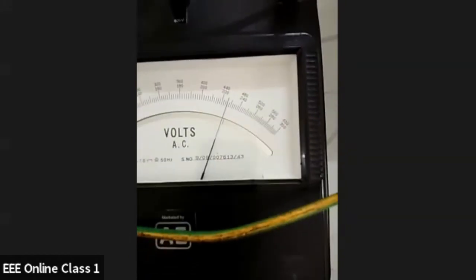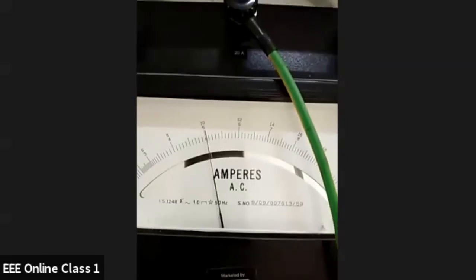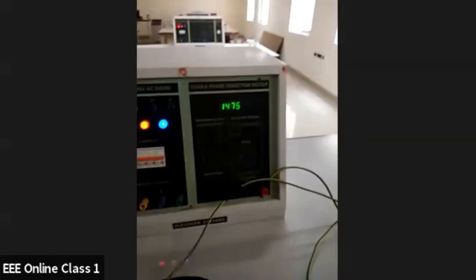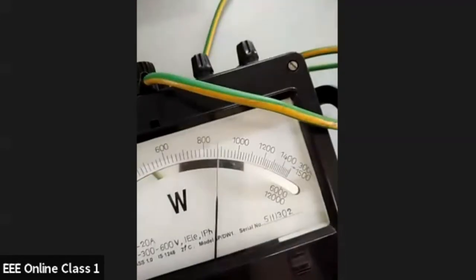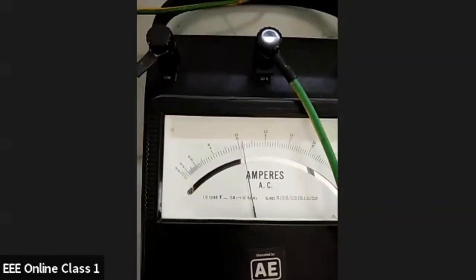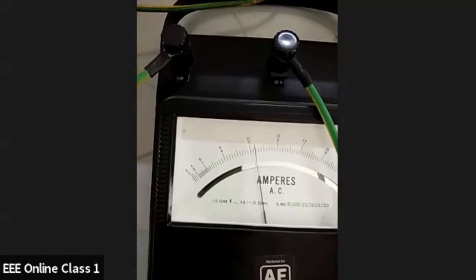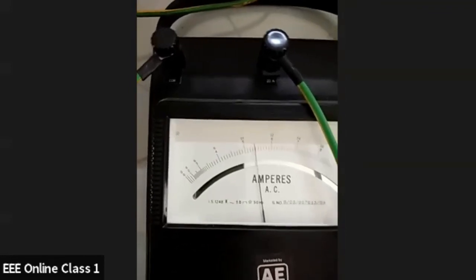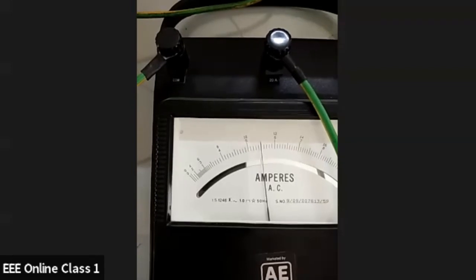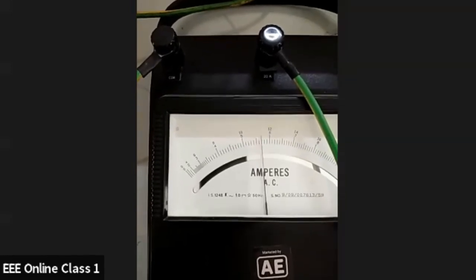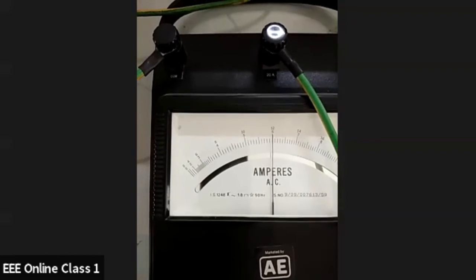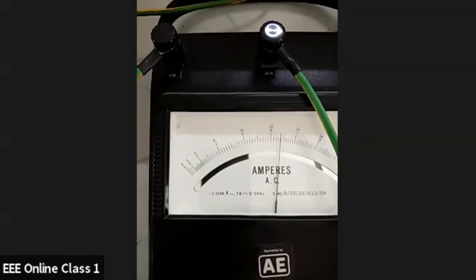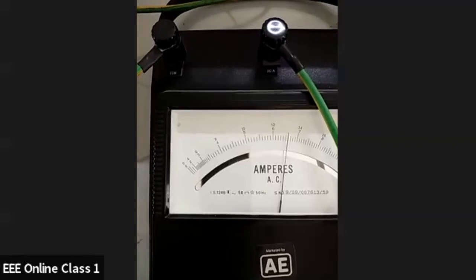For the next load of 10 amperes, corresponding speed is 1475 and the power is 840 watts. So we have to continue this conduction until we reach the rated current of the motor. We know that the rated current of the motor is 13.5. So we can take the readings up to 13 amperes without any trouble. So this is for 11 amperes, then 12 amperes, and the last reading will be for 13 amperes.